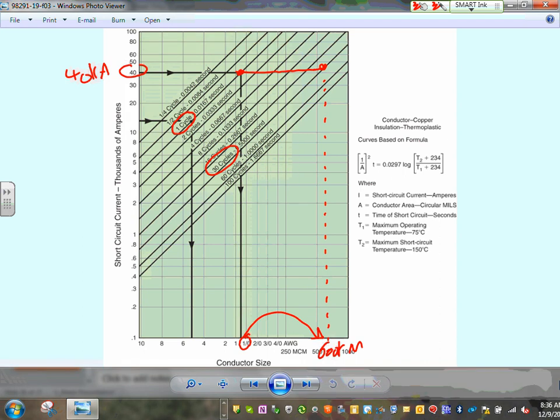So anyway, what I'm going to summarize, guys, is the faster the circuit breaker trips, the better for your equipment. Or the fuse opens, the better for your equipment. Typically, we trip within 3 cycles. In a quarter of a cycle, if it's a current limiting fuse. If it's a circuit breaker, within 3 cycles. Any comments, guys? Any questions? So that chart will show you one thing. The longer you allow the short circuit to sit in your system, the bigger your conductor has to be.